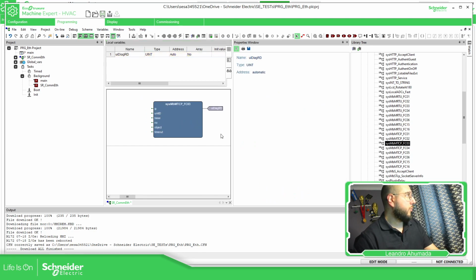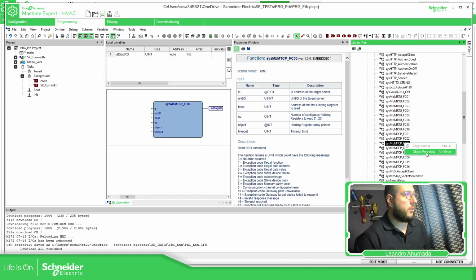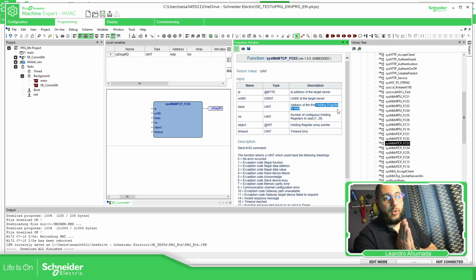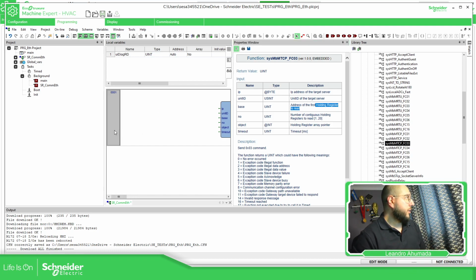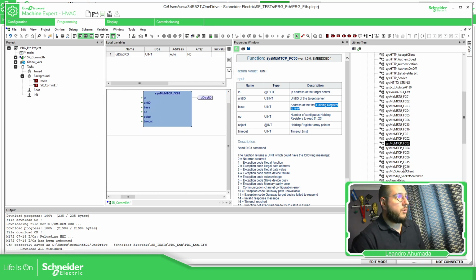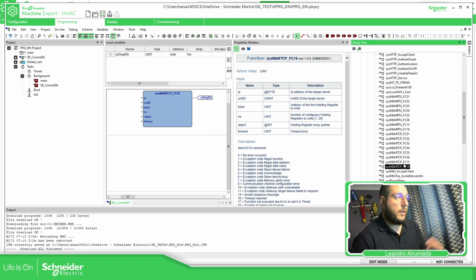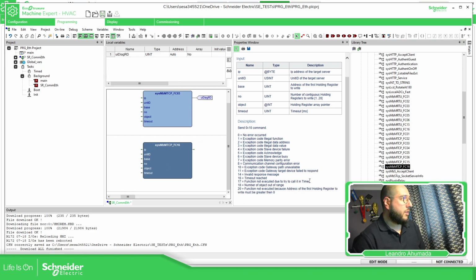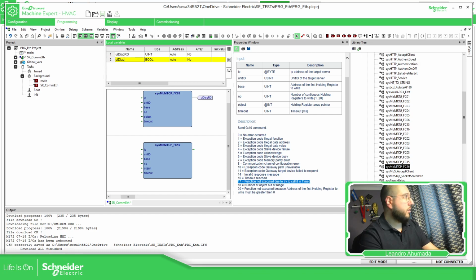Okay. So the FC03, let's use over here, is to read holding register. Okay, so that will read the position MW50 that I want. Now I'm going to create another one over here in order to write information. So in order to write multiple registers, not just one, I need to use this one. So drag and drop. And again, you have here the time task. So I'm going to create another one. Yeah, here we are. Great.